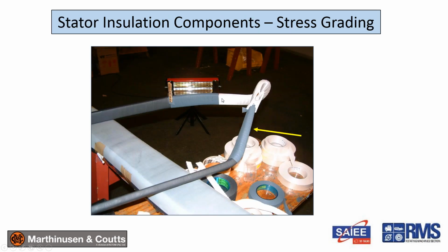And this is a picture showing a partially wound high voltage stator coil. So the black tape is your semiconductive anti-corona layer. It goes in the slot and extends a little bit out of the slot. The gray portion is semiconductive stress grading, so it's almost an electrostatic component. And all of these are important in an insulation system. But again, we're concentrating on the main insulation.